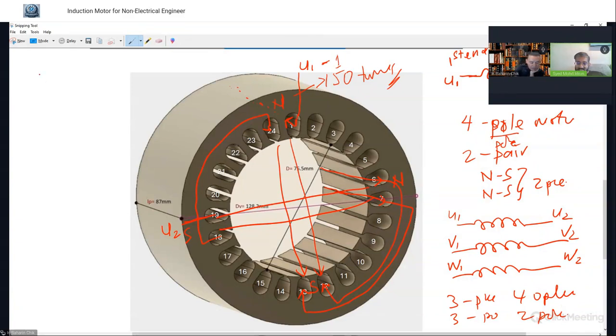Okay. If for example you are talking about efficiency, this is more on how fast you can remove the heat from the motors, right? You remember when we had the AC induction motors that were illustrated, we have got fans at the back, right? So now if you're talking about efficiency, it has got nothing to do with the rewinding of these motors. It is how fast you can remove the heat from this stator core into the environment. So how cool your motor can run. So that is more on the efficiency.